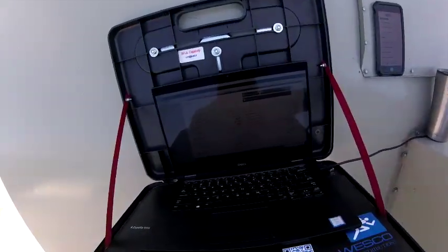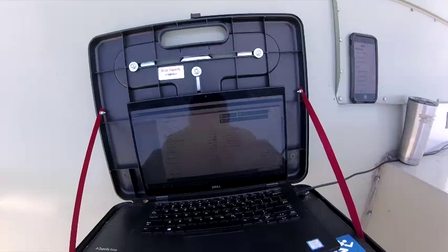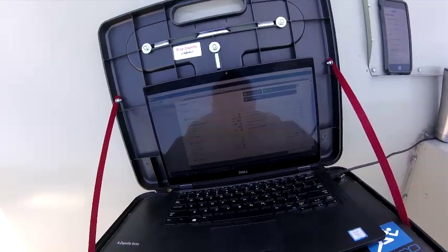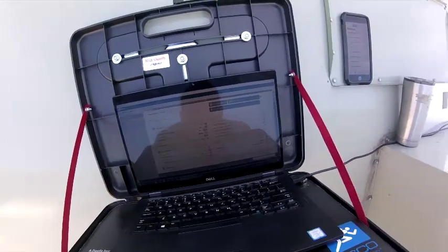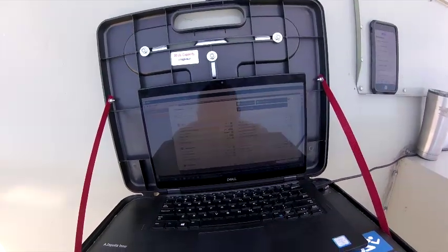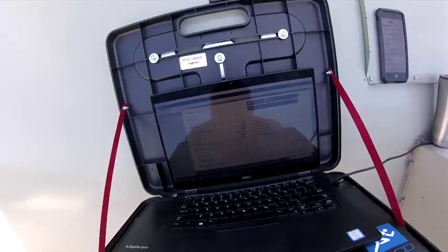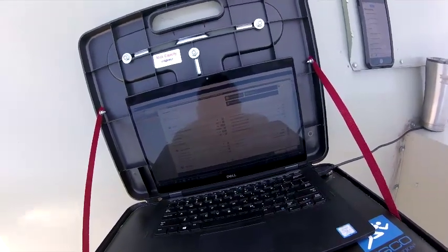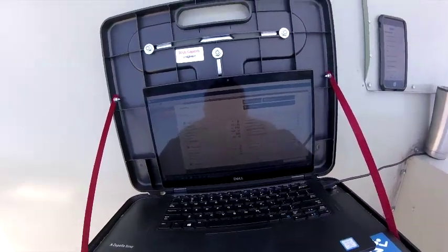All right. So I just spoke with BAS because up here, I can't tell. These have fan power boxes associated with them. I don't know what the space temperature or some of those boxes satisfied from up here. Some of them you might have the dampers closed, some of them may be open. But he's going to give me a call back and let me know which ones are satisfied. Because he said yesterday all the boxes were set for the CFM, because I can't see CFM up here either. The fan power boxes are reading CFM, but I would have to go down there and actually plug into the fan power box to see the CFM. But they was all set for minimum and maximum, the same exact CFM. So just say the minimum was, let's say, 100 CFM, and the maximum was 100 CFM. So they was open all the time.